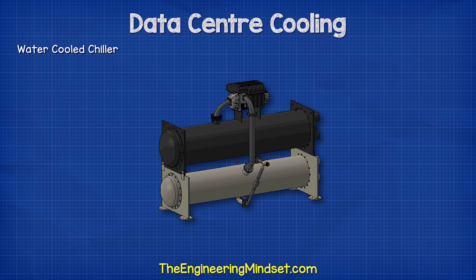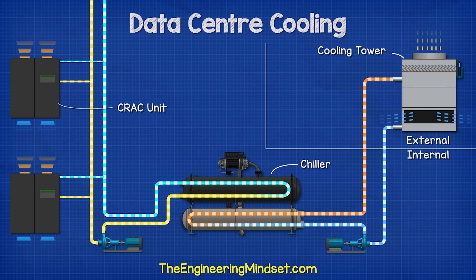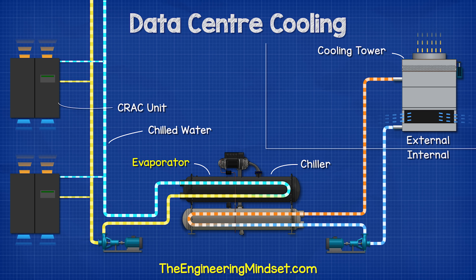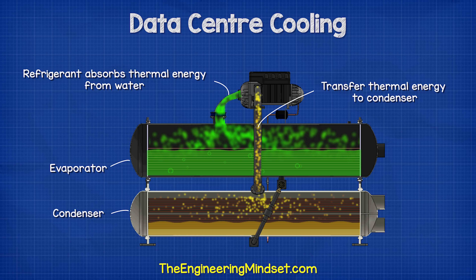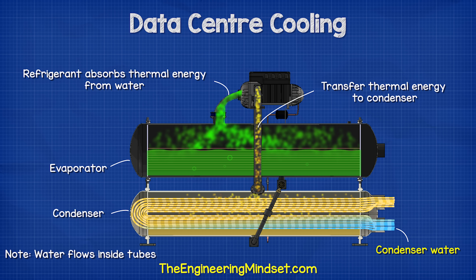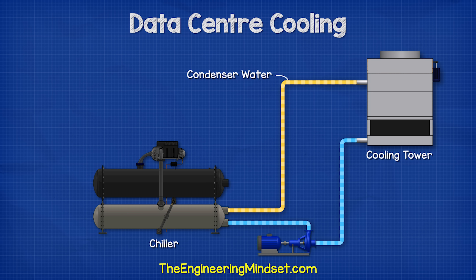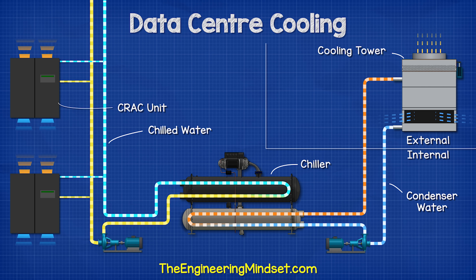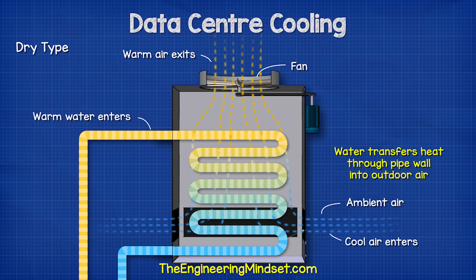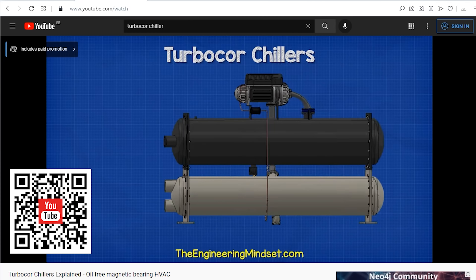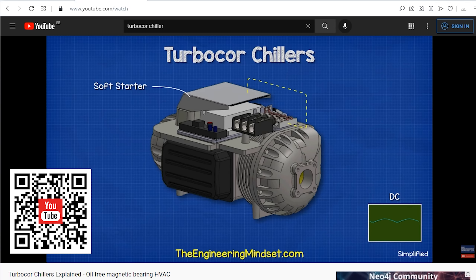With water-cooled systems, the chiller is installed internally with a cooling tower located externally. The chiller sends chilled water to the CRAC unit to collect the unwanted heat, and then returns this to the chiller's evaporator. A refrigerant inside the evaporator collects this heat and transfers it to the condenser. Another stream of water flowing in the condenser, known as the condenser water, absorbs the thermal energy and sends it to the cooling tower, where the water is usually sprayed into a stream of ambient air to remove the heat and cool the water down. The water then returns to the condenser, ready to collect more thermal energy. We can also get dry cooling towers, which are less efficient — the condenser water simply flows through a heat exchanger with air blown over it to remove the heat instead of being sprayed into the airstream. We have covered how chillers work in great detail previously, with links in the video description down below.